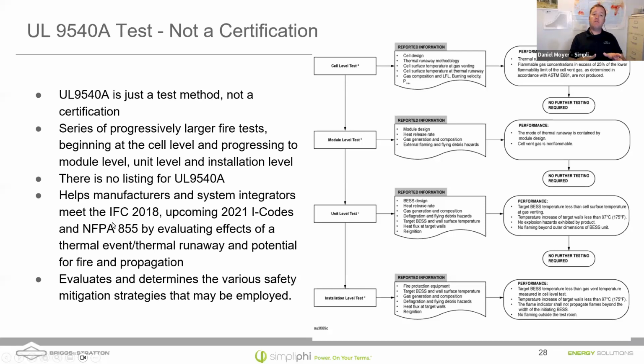Look at the most recent 855 and you'll see that a lot of different manufacturers, if you can show you've done a 9540A test and call it out in your installation instructions, are able to not necessarily ignore 855, but you still have to take it into consideration. A lot of times different jurisdictions interpret 855 and these tests differently, so it's not across the board that you're allowed to do whatever you want if you have 9540A. But if you're able to show you've safely done more compact installations, you can argue that certain specific parts of 855 allow you to circumvent that. I wouldn't be able to go fully into it here - email me and we can jump into that a little deeper.